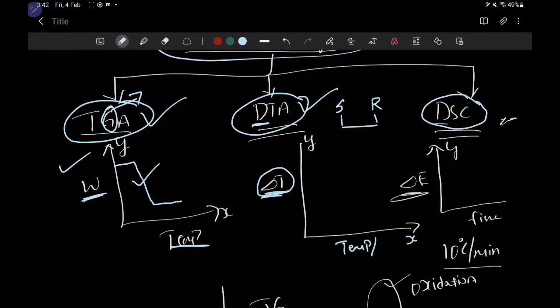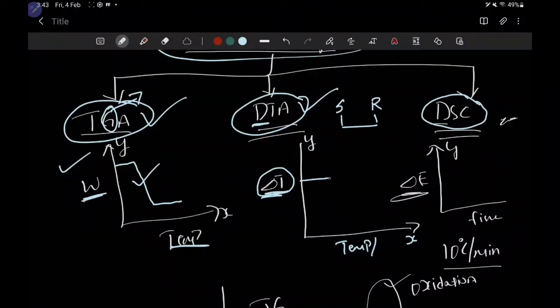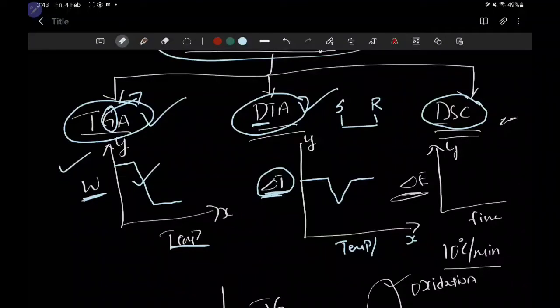As temperature increases, there will be no change in the temperature difference between your sample and reference — meaning they both remain at the same temperature. Once the sample undergoes an exothermic or endothermic reaction, the graph will change accordingly. If it is endothermic, the graph will show a dip and then recover. Depending on the reaction the sample undergoes, the graph changes — this is called differential thermal analysis.